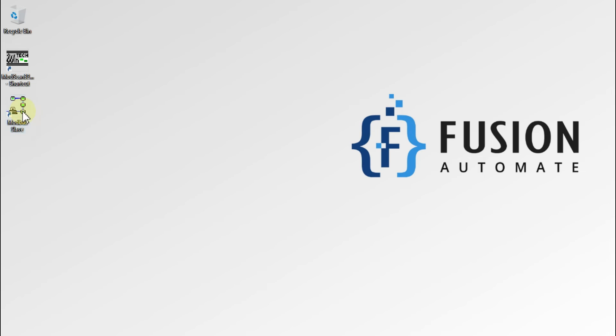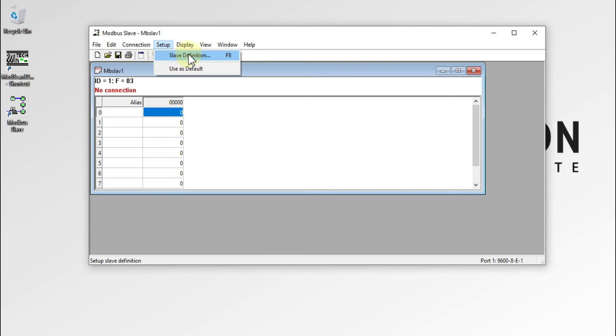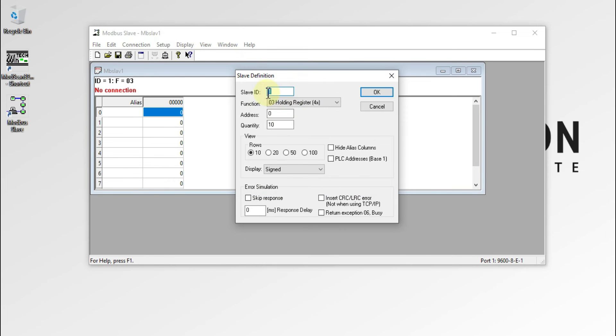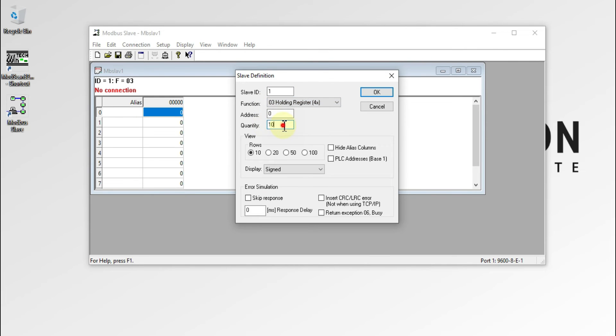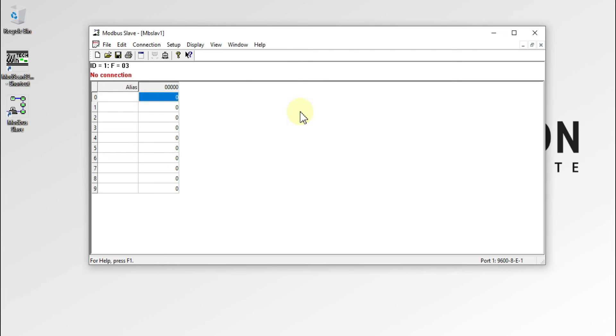Let's open Modbus Slave. You need to specify what type of Modbus TCP server you want to create. Suppose I want to create a server with slave ID 1 and 10 holding registers. Go to Setup, then Slave Definition. Set the slave ID to 1, function code to 3 for holding registers, and quantity to 10, then press OK. You can see there is no connection yet because the server is not running.